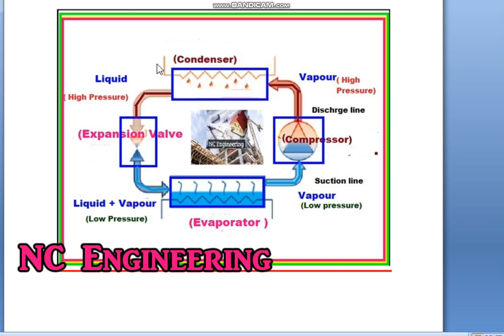After the condenser, the high pressure liquid refrigerant passes through number 3 — the expansion valve or throttling valve — which reduces the pressure abruptly, causing the temperature to drop dramatically. So this high pressure liquid, when it passes through the expansion valve, converts to a mixture of liquid plus vapor at low pressure.